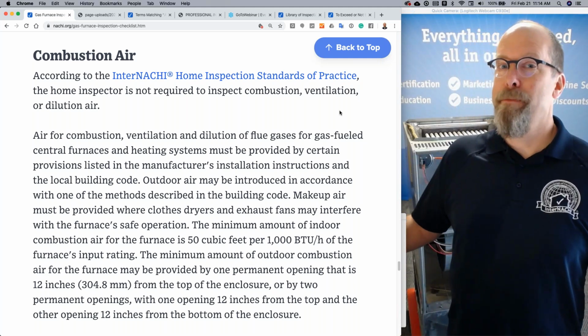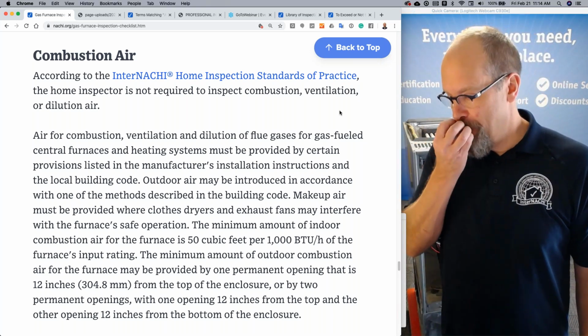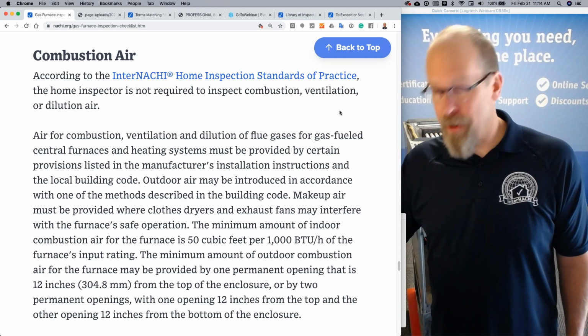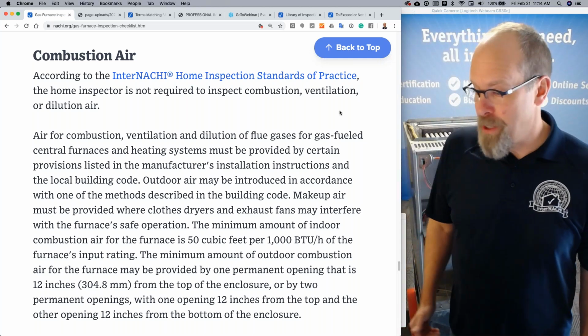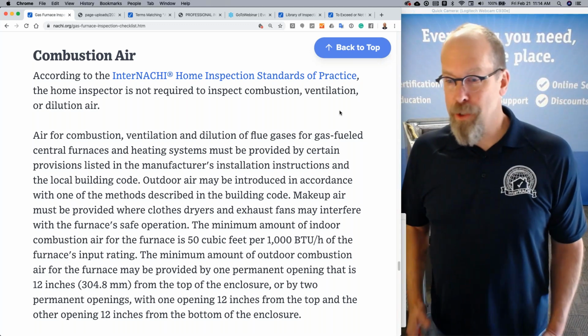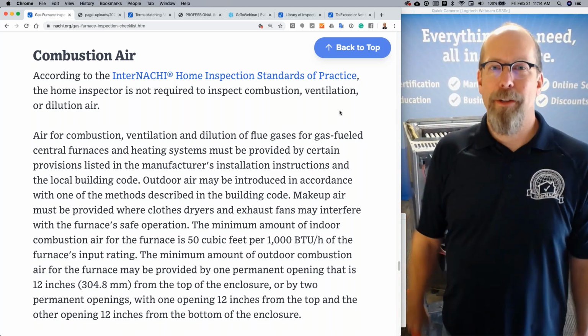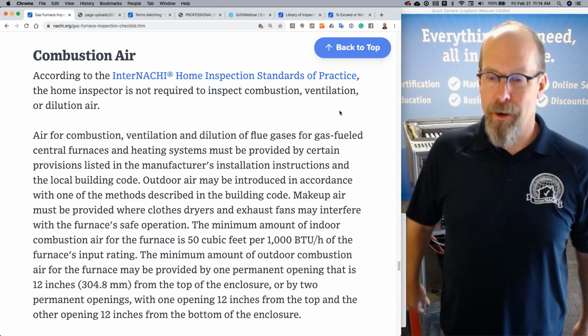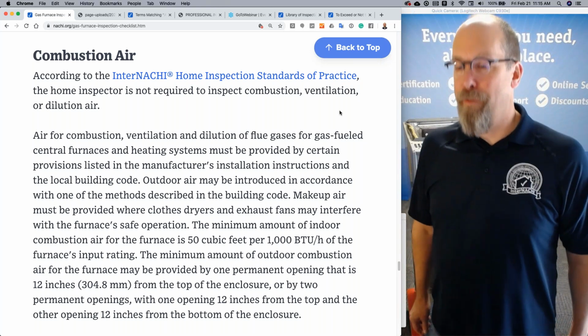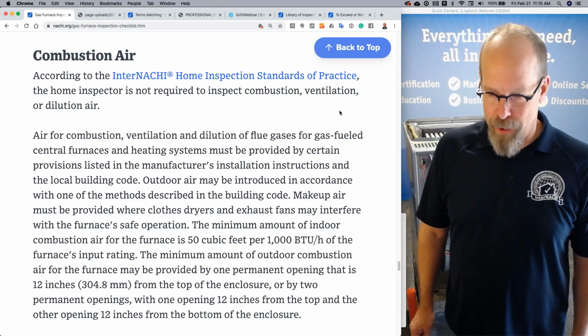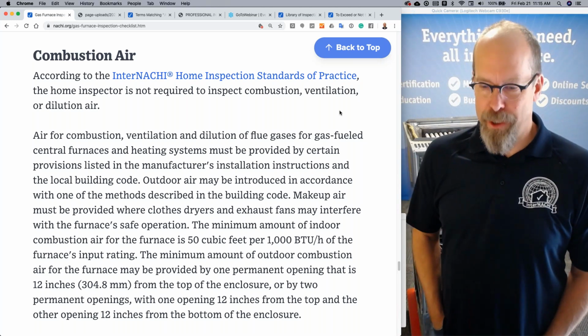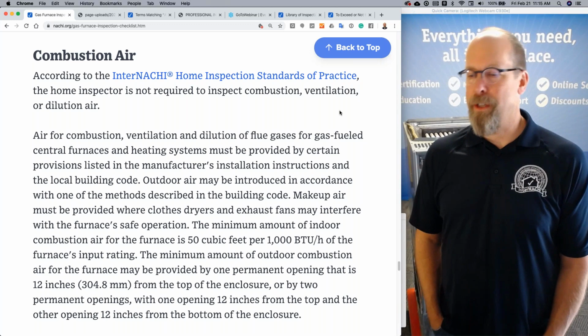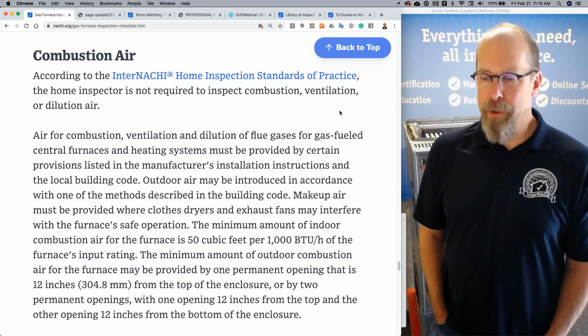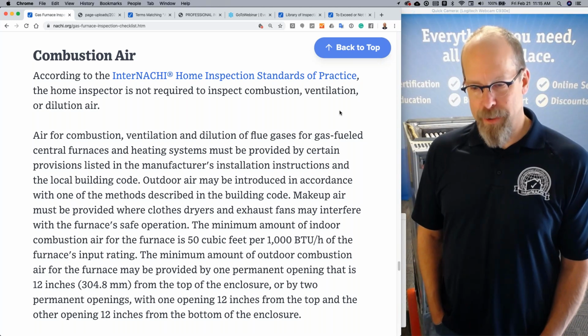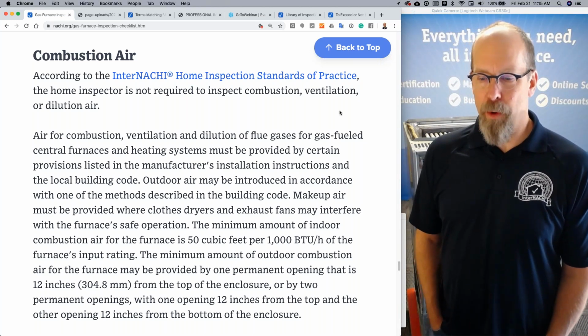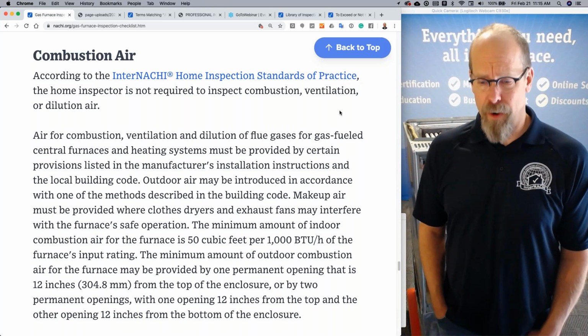But again, INTERNACHI, an accredited home inspector college, we abide by national standards, just like all other accredited schools. And we're required to teach updated current curriculum. So that's why we went to the code book just for a moment and talked about those three things: combustion, ventilation, dilution air. Air for combustion, ventilation, and dilution of flue gases for gas-fueled central furnaces and heating systems must be provided by certain provisions listed in the manufacturer's installation instructions, which we looked at before, and the local building code. Outdoor air may be introduced in accordance with one of those methods described in the code. Makeup air must be provided where clothes dryers and exhaust fans may interfere with the furnace's safe operation.